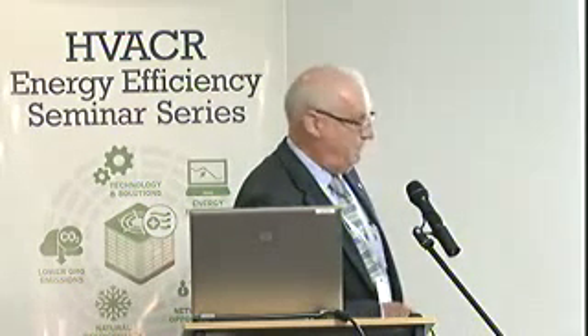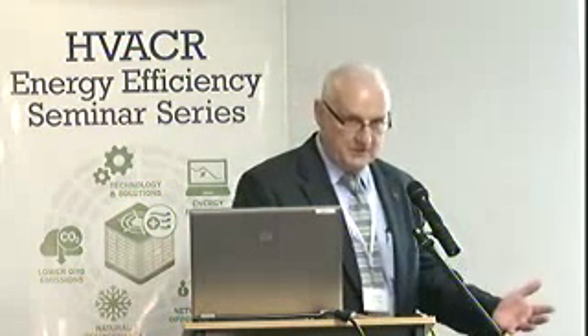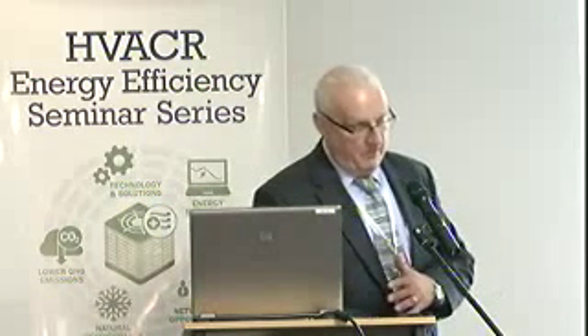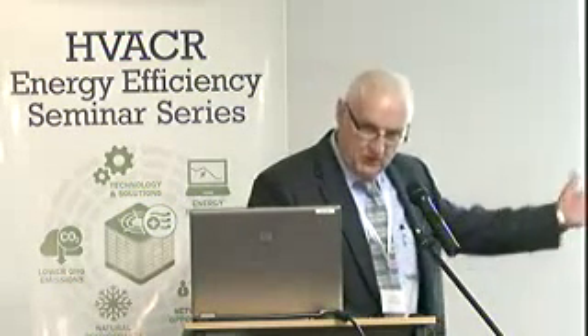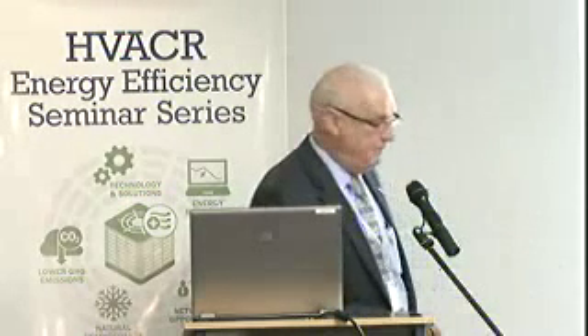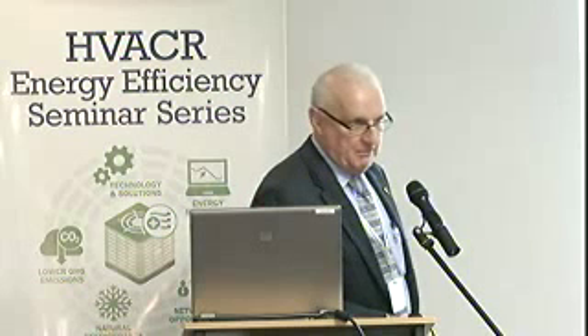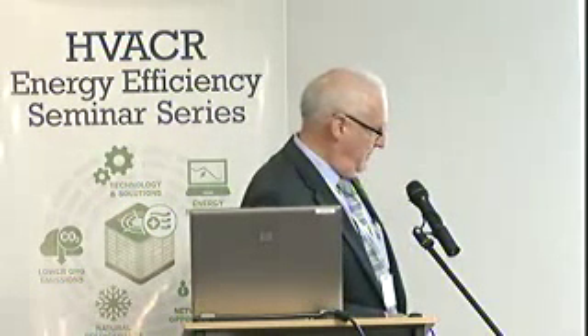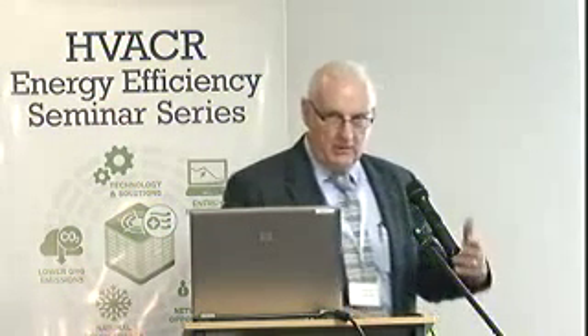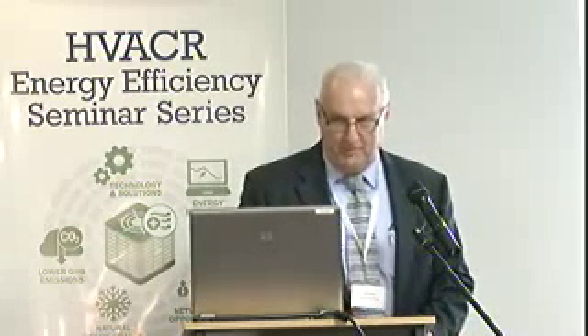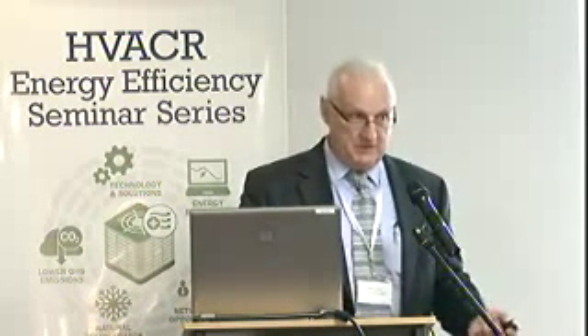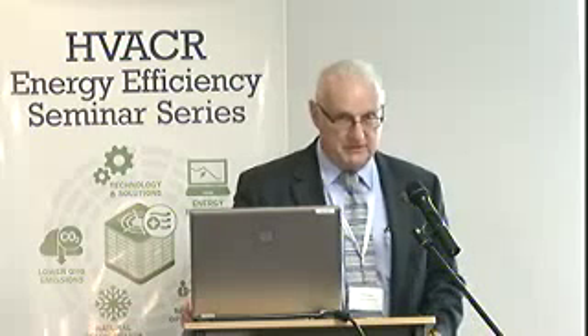When we install power factor correction or capacitance, which is the opposite of a motor and inductance, and it's the motors that are causing most of this bad power factor, then we tend to bring these two waveforms into alignment, maybe not as perfectly as I've shown there, but that's the objective. But the other thing that happens is you'll notice that the current has reduced. So it's an opportunity to improve the capacity of a switchboard, as well as to reduce the demand charges where you've got a kVA maximum demand charge.